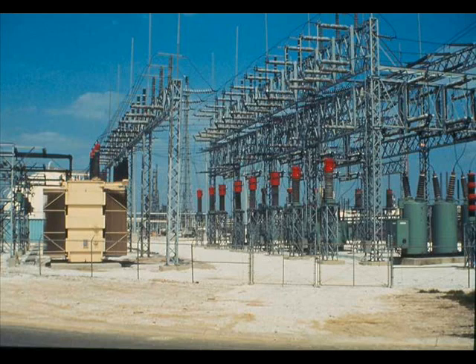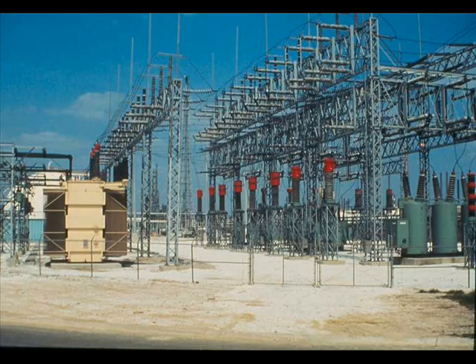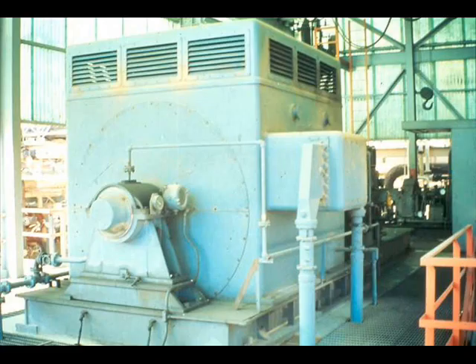Others carry 13.8 kV electricity to the plant's power distribution centers. The refinery has nearly a dozen, identified as PDC-1, PDC-2, etc. Each PDC is served by two 13.8 feeders. Pairs of PDCs are connected to reduce the effect of losing one or more of the 13.8 feeders. In a few cases, a feeder from a PDC powers a single piece of equipment — for example, one feeder is dedicated to a 9,000 horsepower compressor motor.